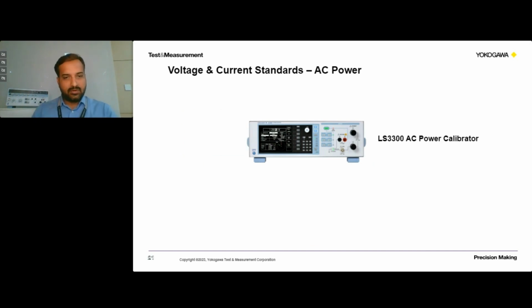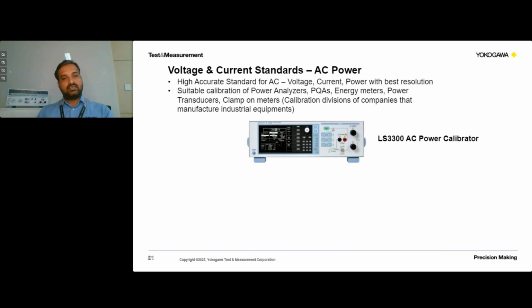Next we have the AC power calibrator model called LS3300. As you can see here, it is a calibrator which covers both voltage and current. Along with that, it has the capability to do power calibration with the best possible resolution. So this is the most suitable master standard for calibration of power analyzers, power quality analyzers, energy meters, power transducers, those kinds of DUTs. And for people who are into the manufacturing of industrial equipment, such as voltage indicators, current indicators, and energy meters for panels, or low range power quality analyzers, energy loggers, those kinds of instruments, this product is a must have for those kinds of customers.